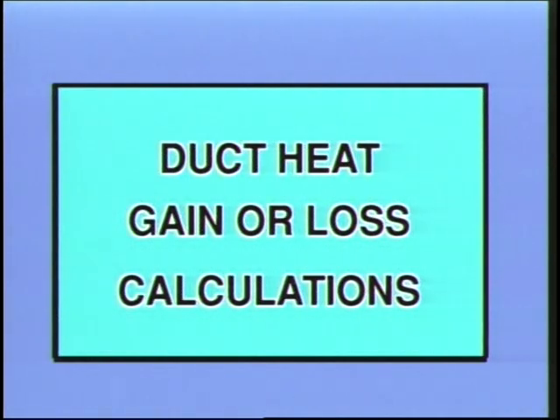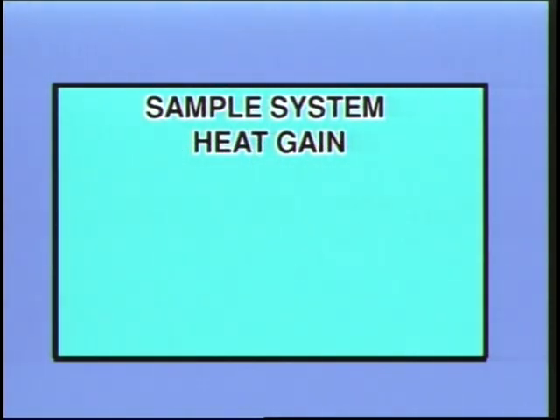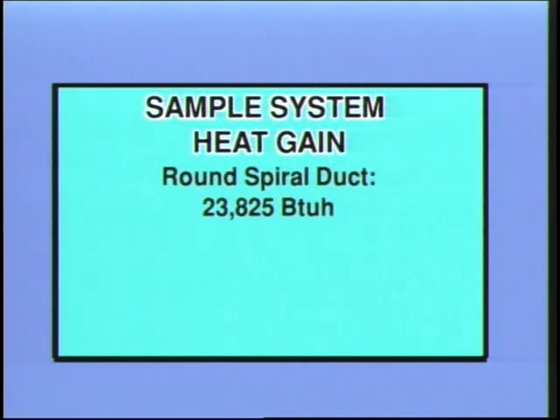Duct airflow heat gain or loss also is based on the amount of duct system surface, as well as other factors such as the temperature difference between the duct airstream and the surrounding ambient air, and the duct airflow velocity, which is a function of the duct cross-sectional area. The approximate duct heat gain calculations for the same sample HVAC duct system constructions follow below.